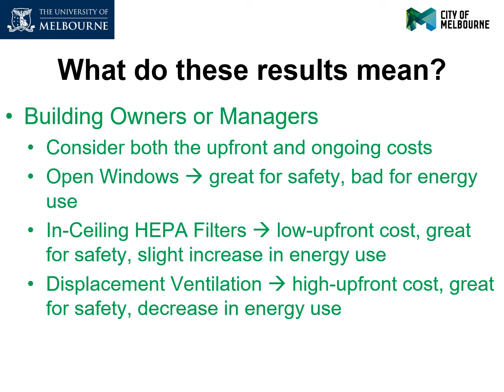Displacement ventilation: retrofitting the space for displacement ventilation was the largest upfront cost option for both increasing ACHE and the safety of the space. This option also had the smallest increase in ACHE, but the largest reduction of modeled aerosolized virus spread. The reason for these seemingly contradictory findings is that displacement ventilation was found to greatly reduce how far aerosols would spread, effectively reducing the population of the space.